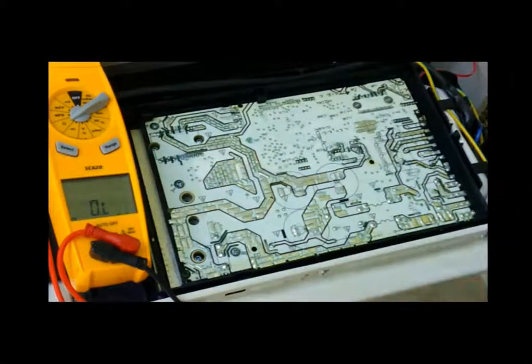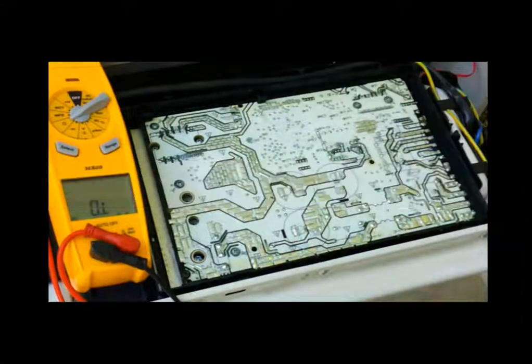So if this was a true error that we had in this board, then that would be the problem. We would see irregular readings either on our capacitors, which means that the power module is burnt out, or it would be with our gates, which means that they are burnt out. They're thermally protected and they're opened up. At that point, if they're opened up, we're going to let this thing cool down for a couple of hours, put it back into service and see if it takes back off. If it doesn't, we're going to simply replace the board on this series.